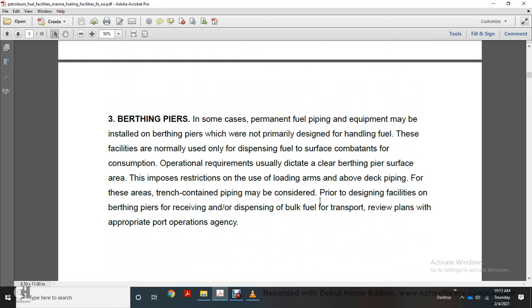3. Berthing piers. In some cases, permanent fuel piping equipment may be installed on berthing piers that were not primarily designed for handling fuel. These facilities are normally used only for dispensing fuel to surface combatants for consumption. Operational requirements usually dictate a clear berthing pier surface area. These impose restrictions on the use of loading arms and above deck piping. For these areas, trench-contained piping may be considered. Prior to designing facilities on berthing piers for receiving and dispensing bulk fuel for transport, review plans with the appropriate port operation agency.